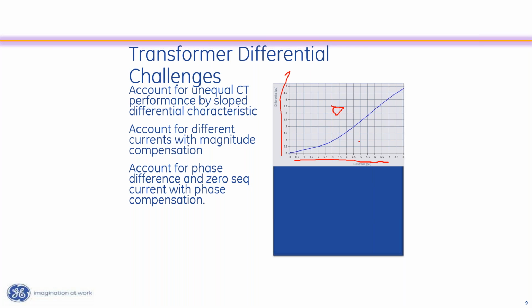So let's talk about that actual fault. In that actual fault, I had differential current of 10 per unit at 0 degrees. Now, I haven't defined what restraint is. What restraint actually is, is the maximum of the two currents on the zone of protection. So if I've got, let's say instead of a 10 per unit fault, a 5 per unit fault, my restraint's right here.